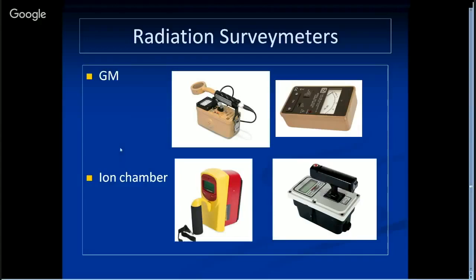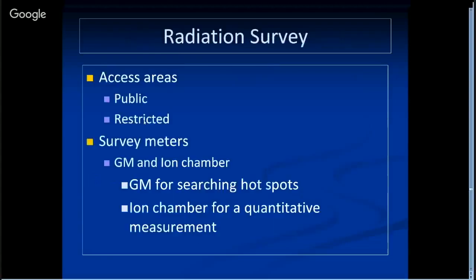For radiation survey you need survey meters. Usually you need two kinds: the GM survey meter and the ion chamber. The GM survey meter can find a hot spot, and the ion chamber can give you data quantitatively.